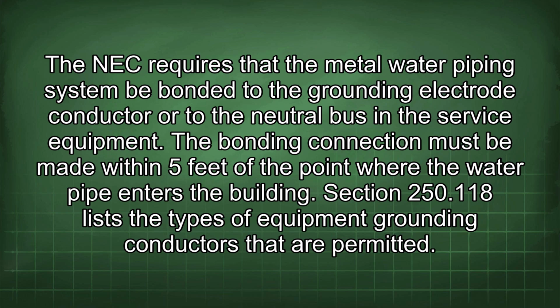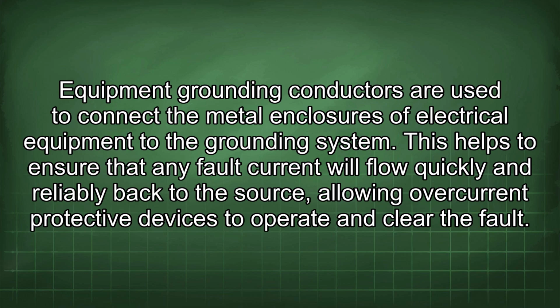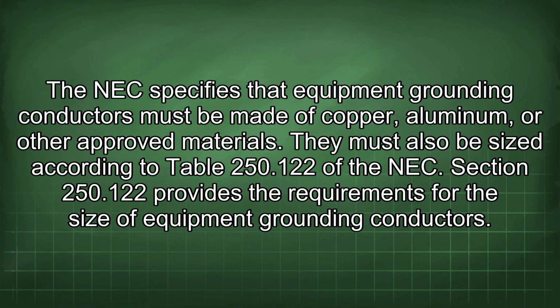Section 250.118 lists the types of equipment grounding conductors that are permitted. Equipment grounding conductors are used to connect the metal enclosures of electrical equipment to the grounding system. This helps to ensure that any fault current will flow quickly and reliably back to the source, allowing overcurrent protective devices to operate and clear the fault. The NEC specifies that equipment grounding conductors must be made of copper, aluminum, or other approved materials. They must also be sized according to Table 250.122 of the NEC.